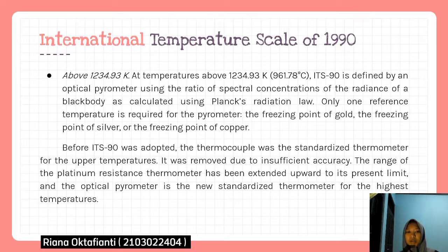Only one reference temperature is required for the pyrometers: the freezing point of gold, the freezing point of silver, or the freezing point of copper.